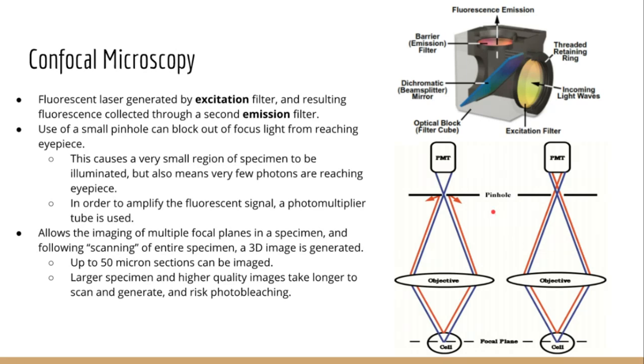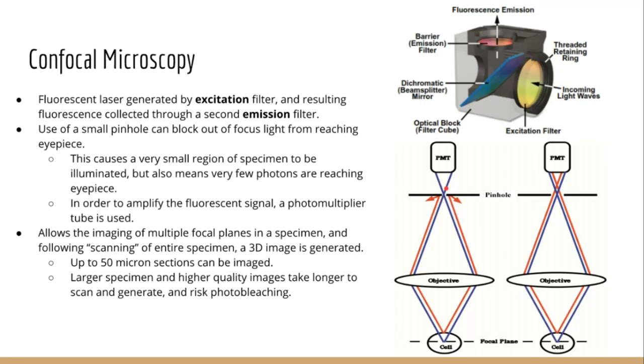The fluorescent confocal microscope was a significant improvement that helped correct this problem. It has an extremely small pinhole that the light is funneled through, which blocks out-of-focus light. Out-of-focus light is blocked because it's not in the right imaging plane, so only in-focus light is collected. This poses a second problem however: as the pinhole gets smaller, although the focal resolution gets better, it also reduces the number of photons being collected. The pinhole restricts light to a very specific area of the specimen but also significantly reduces the intensity of the light.